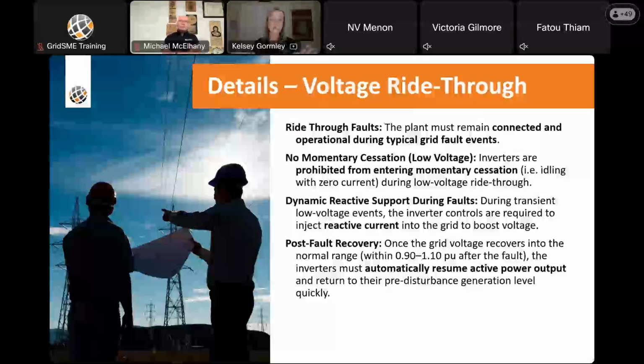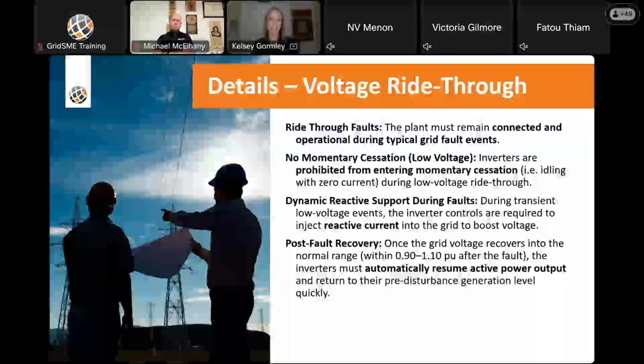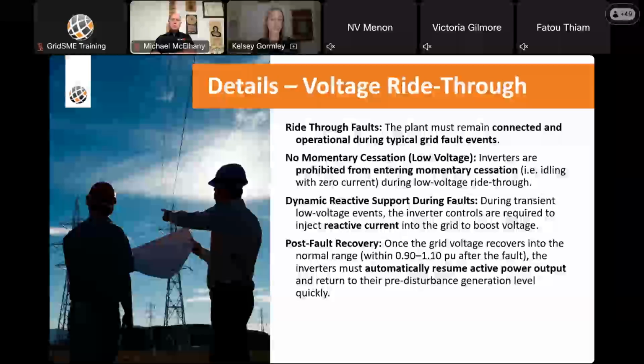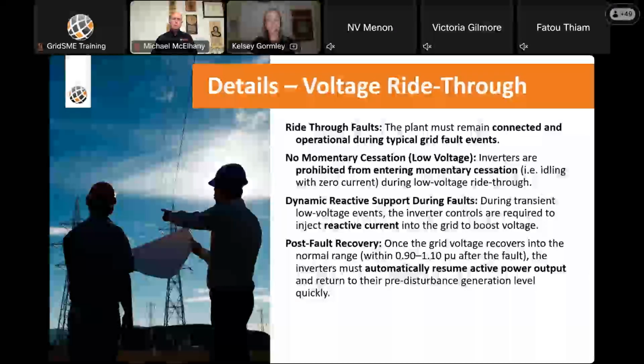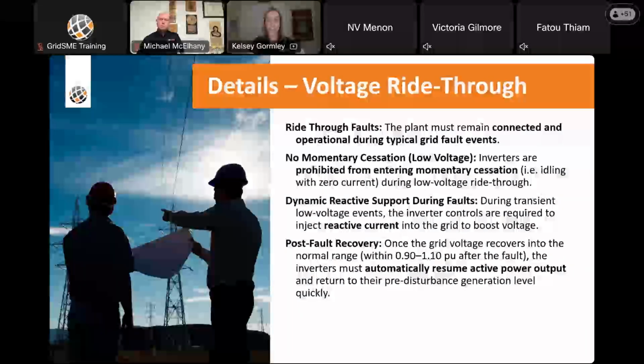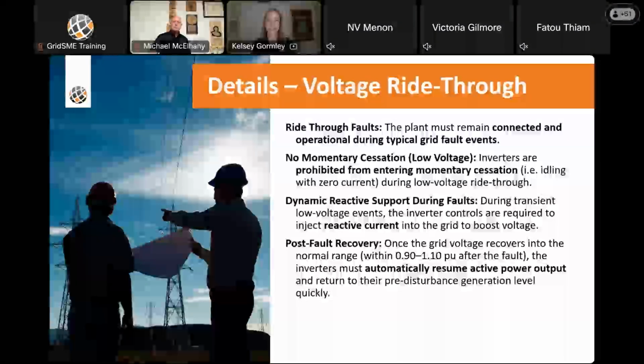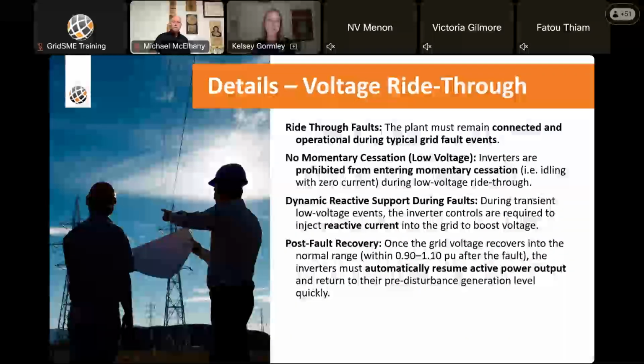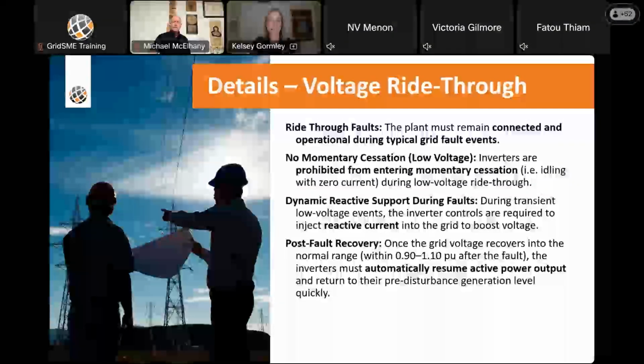So in practical terms, there is no tripping allowed for any common grid fault cleared within normal protection times. This is to avoid widespread generation loss and impacts to the grid. Appendix H explicitly disallows ceasing current injection for undervoltage conditions. The inverters must stay electrically connected and actively support the grid during this dip. Momentary cessation is only permitted for extreme overvoltage events above 1.20 pu, and that's just as a protective measure.